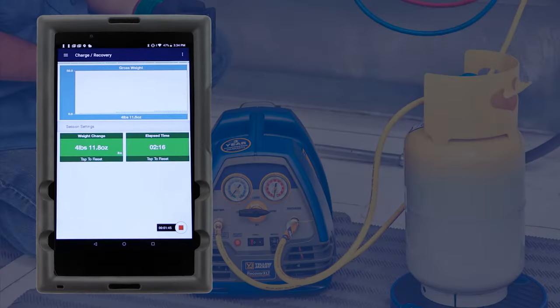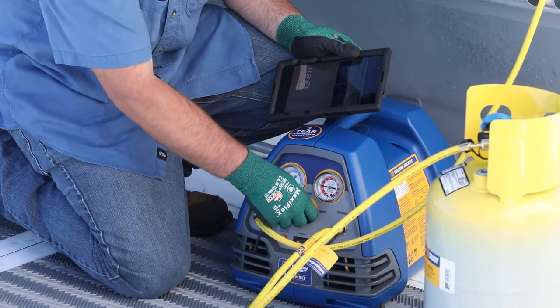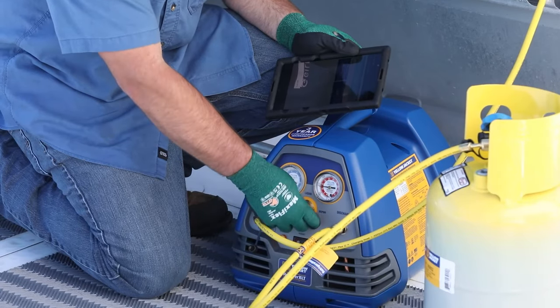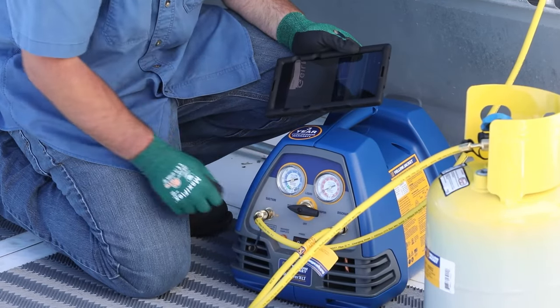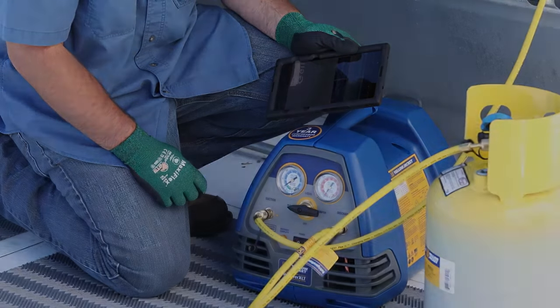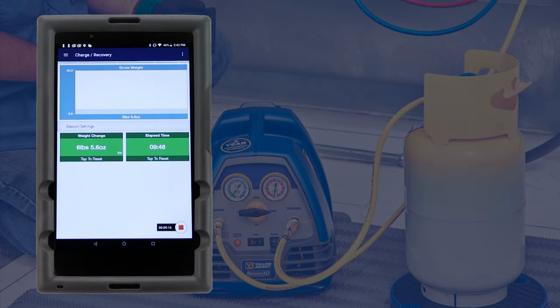Once the system has reached the proper vacuum level, the Recover XLT will automatically power off. Turn the valve to the purge position to purge any refrigerant that is settled in the recovery machine condenser. This is a unique feature you won't find on other recovery machines.